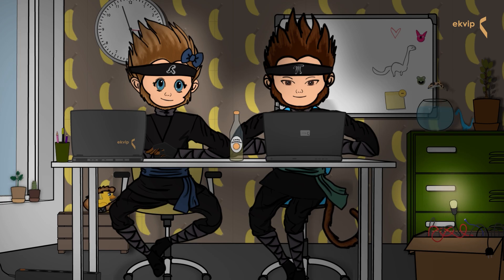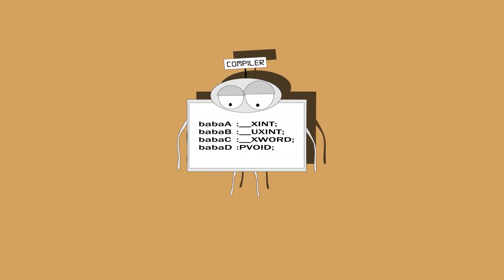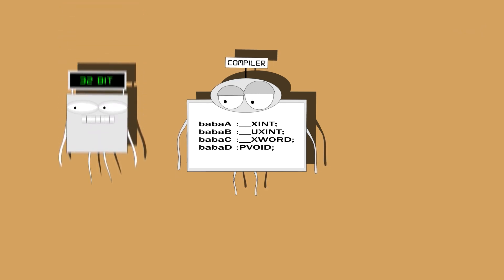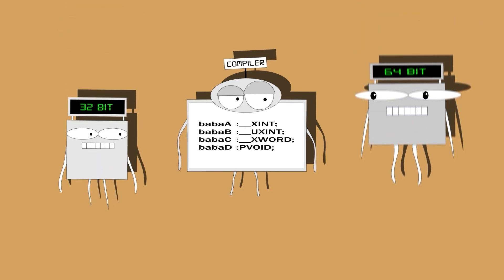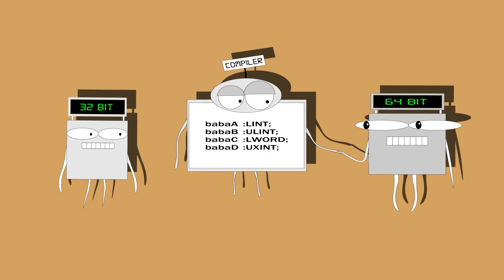These data types belong to a special category where variables are converted to a platform-compliant data type depending on the target system. They make the IEC code as independent as possible from the target system. TwinCAT supports systems with address register widths between 32 and 64 bits. When connected to a target system, the compiler checks which type is used and converts the pseudo data types to the respective standard data types.